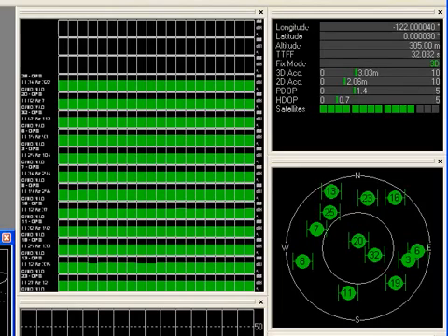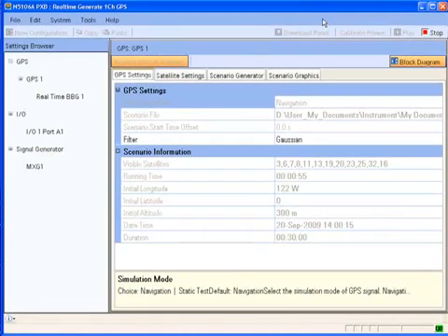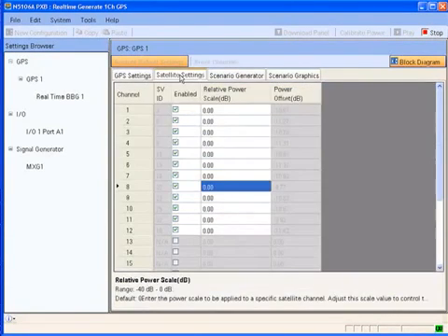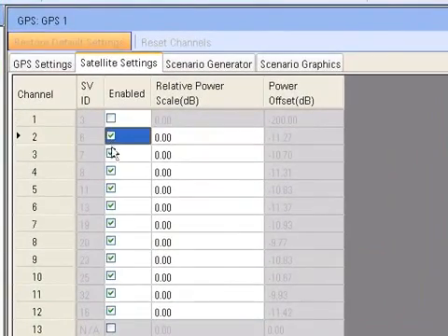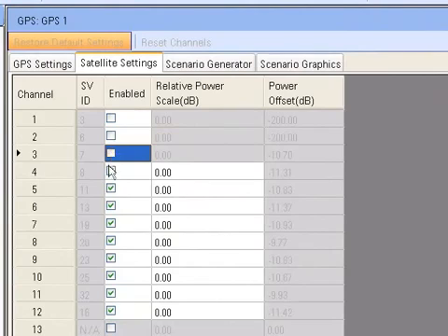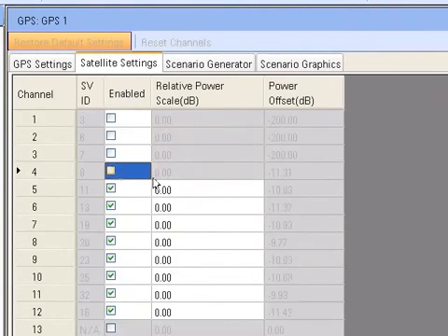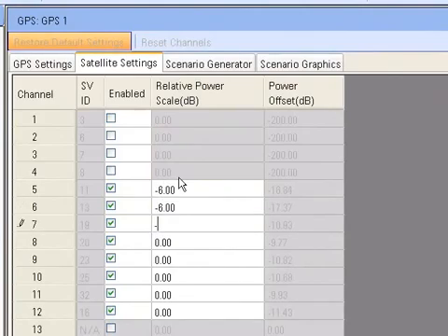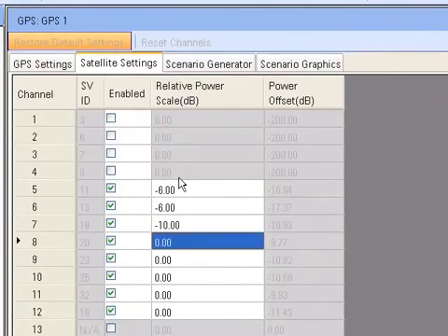Because this is a real-time GPS signal, we can change the visibility and relative power settings of the individual satellites while the signal is playing using the satellite settings tab. Here, we can turn off the visibility of some of the satellites and lower the power on others by 6 and 10 dB. The resulting signal is shown on the U-Center software.